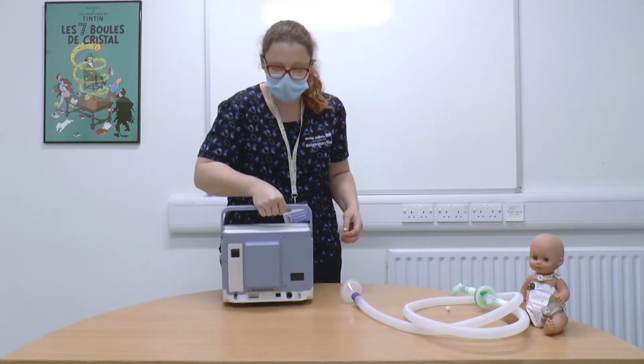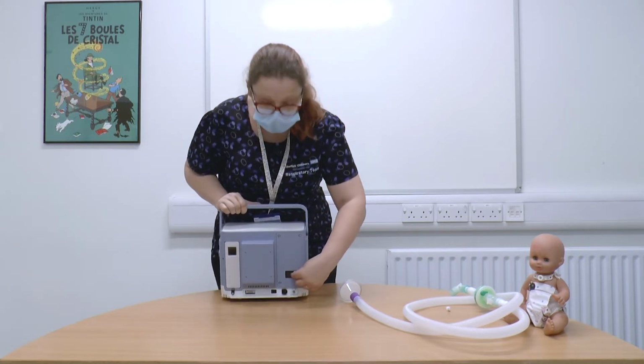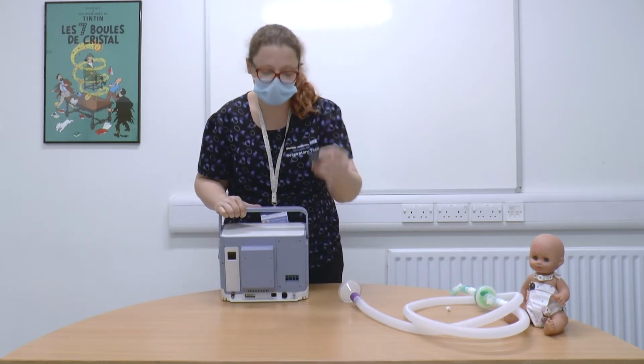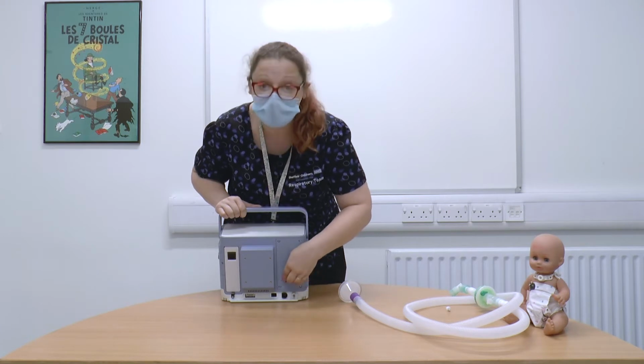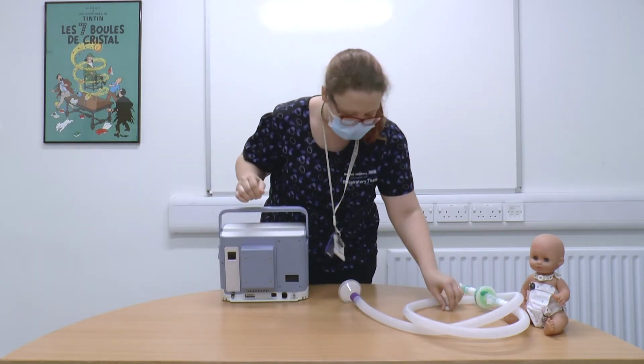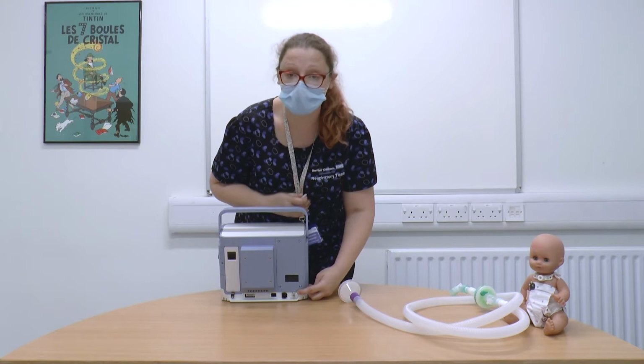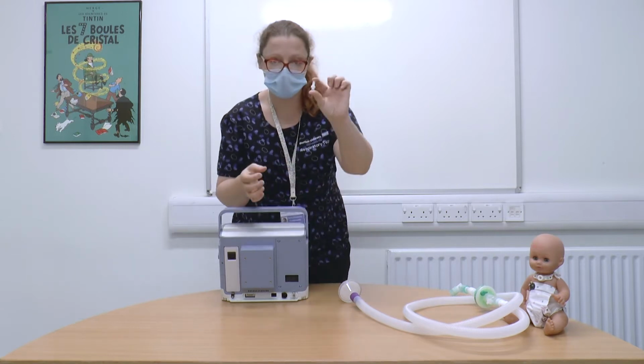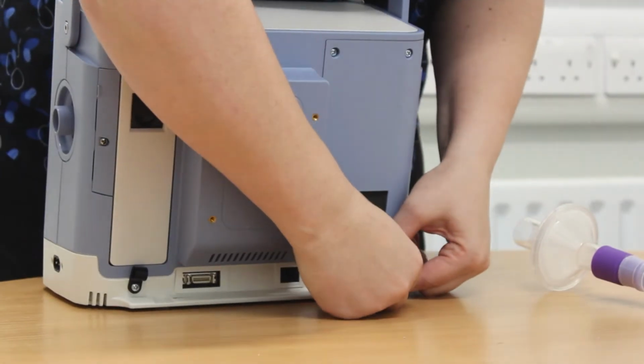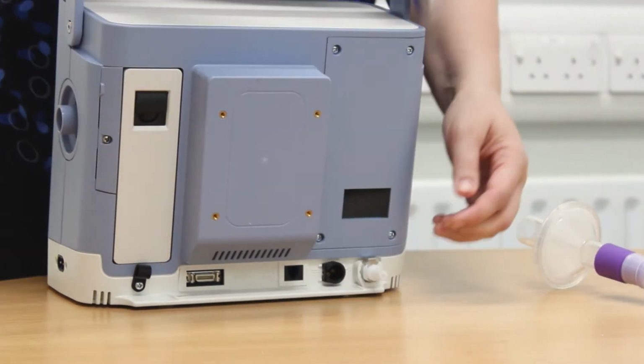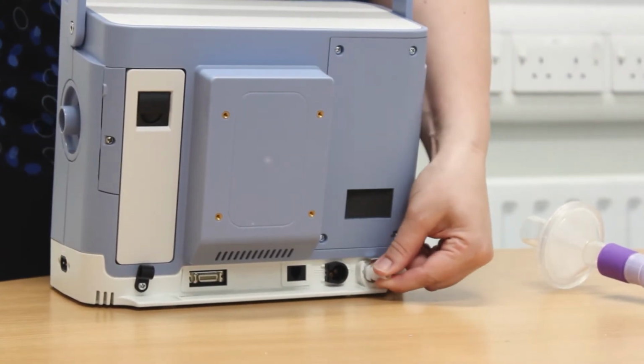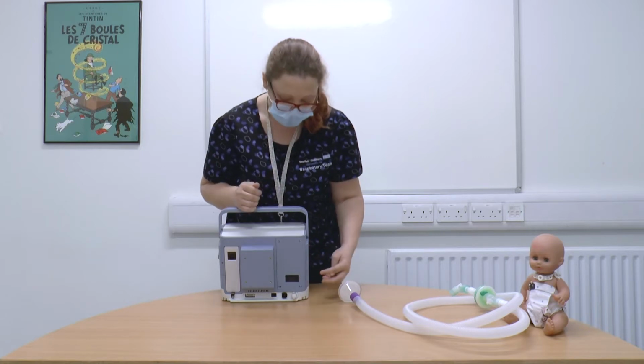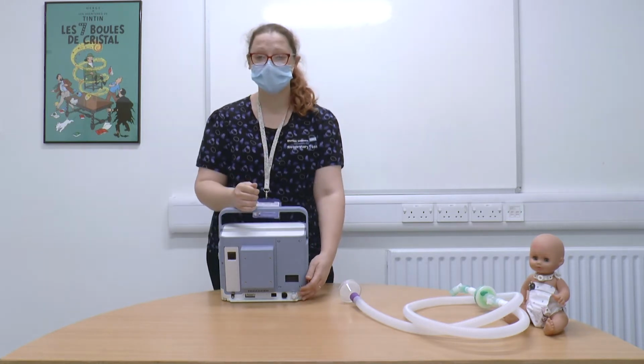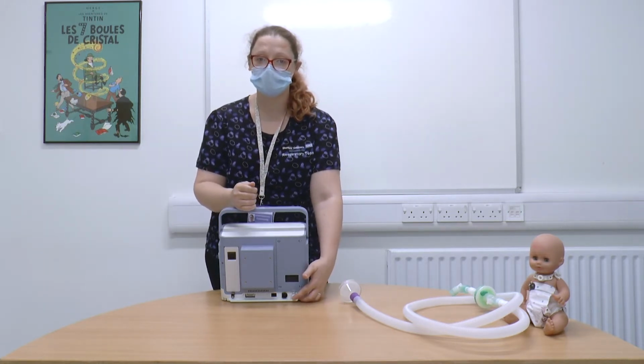At the rear of the ventilator is a filter. That needs to be removed and washed every week. Never put a wet filter back in. You may have an oxygen port. It's a small white piece of plastic. You press the metal down, the plastic insert, give it a gentle tug and it should come out. You can put in up to 15 litres of oxygen through an oxygen port here.